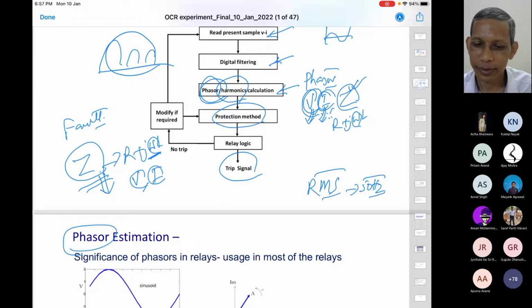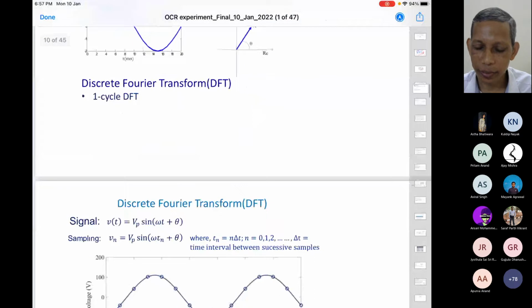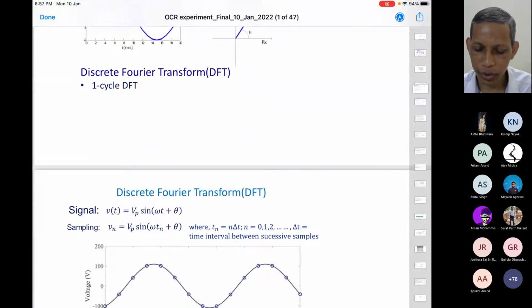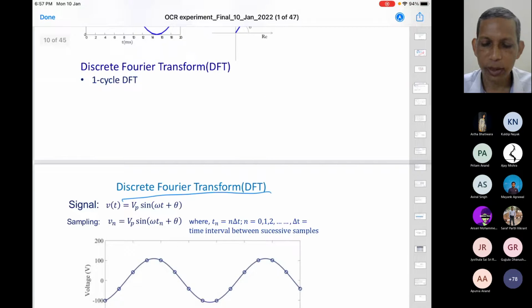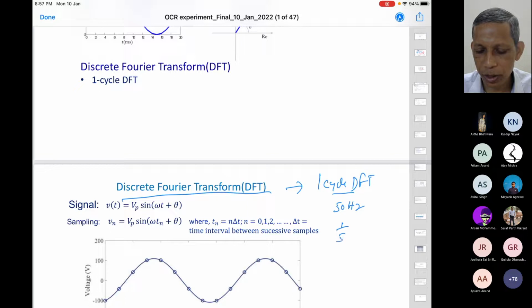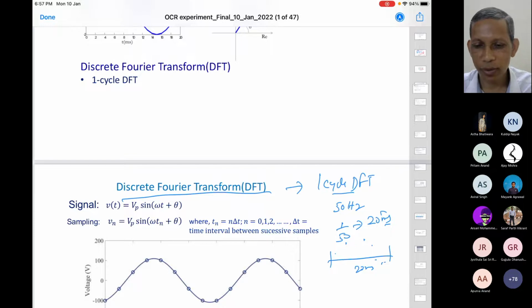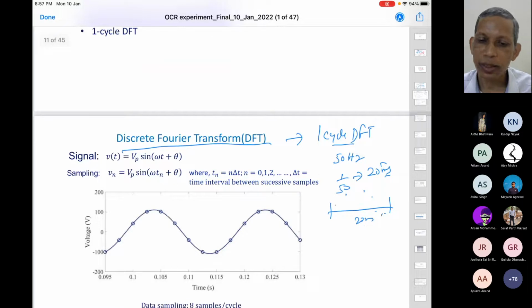So you have to extract their corresponding fundamental from that distorted signal. Agree? Fine. To do that, the typical algorithm is a Fourier-based algorithm, which we call the discrete Fourier transform algorithm, rather, the one cycle DFT. One cycle in a 50 Hz system is 1 by 50, which corresponds to 20 milliseconds. So we take a window of 20 milliseconds, get the corresponding samples, and use them to extract the fundamental component.